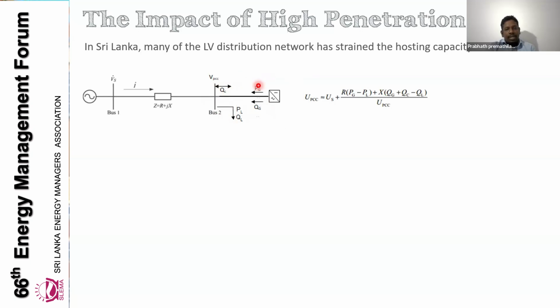For the LV network, as per these equations, the voltage at the point of common coupling is the supply end voltage plus something. So PG minus PL, the active power generation minus consumption, will impact the point of common coupling voltage. In the current context in Sri Lanka, most of the net metering and net accounting consumers have installed higher capacity solar PV systems. In the daytime, they use the CEB network, the utility network, as storage, and they feed to the network. So PL is almost minimum or maybe zero, so the voltage is increasing.